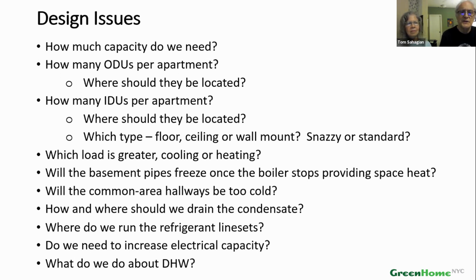A related question was about the common area hallways. There's one large steam radiator on the first floor that was no longer going to be in use, so would the hallways be freezing cold? The answer was also no—the lowest temperature we measured in the hallways was around 60 or 62 degrees. And let's face it, not many people spend much time in the hallway anyway, so it turned out to be a non-issue.